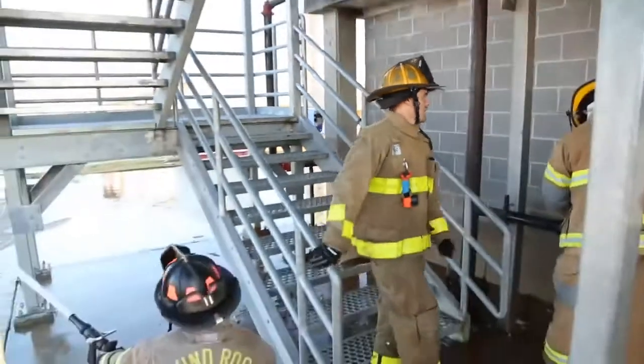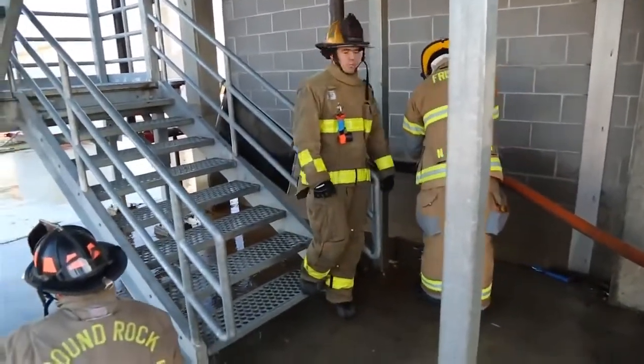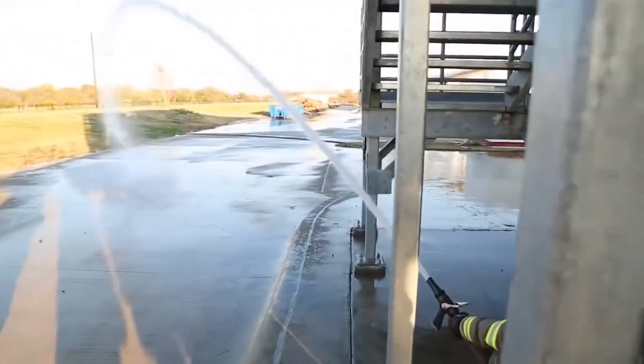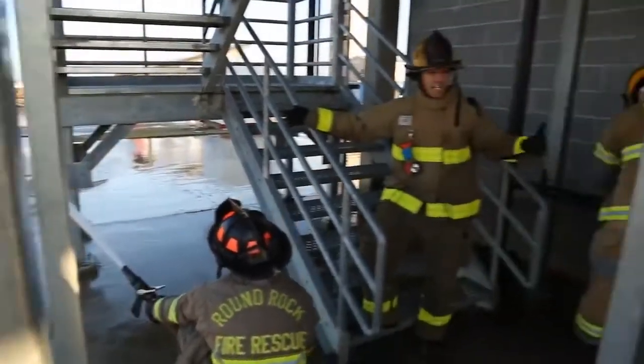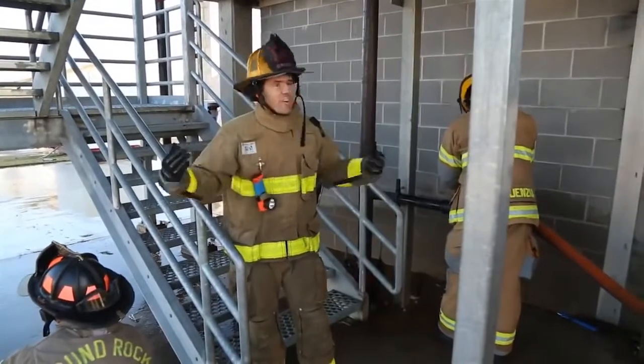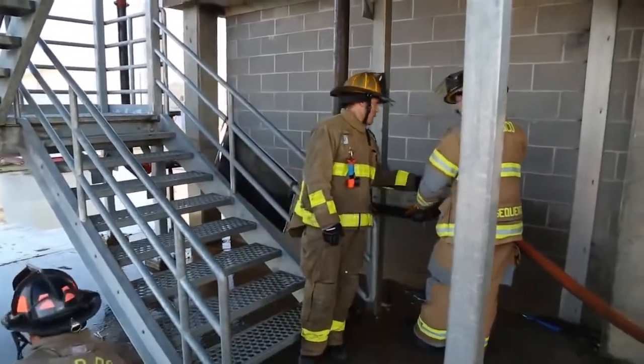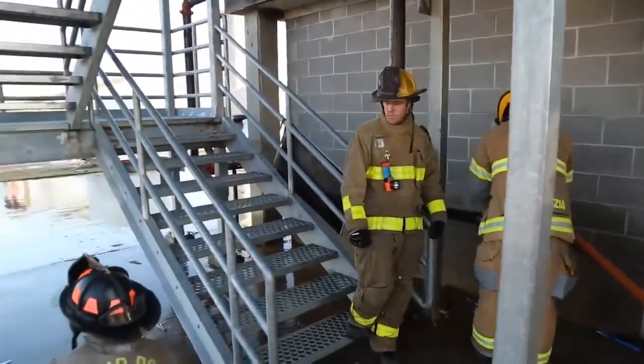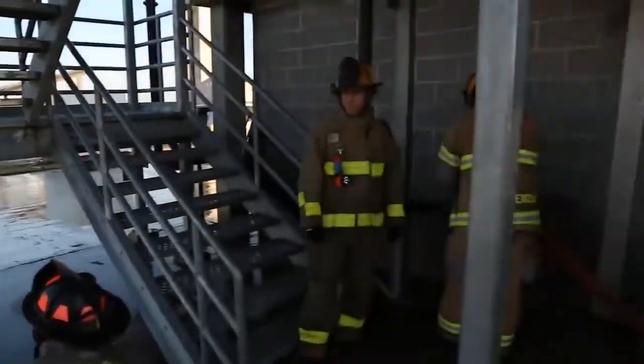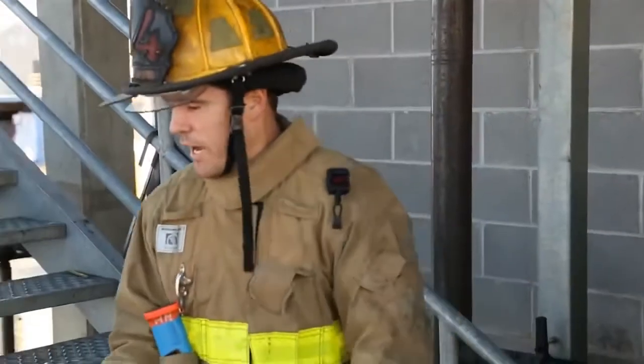What do you see on there? What are we reading? Zero. So almost nothing, right? So keep opening. We have water at the nozzle? Yep. Is that a good stream? I don't like it. That's why we're going to keep flowing. So we're in a stairwell right now, and water is everywhere. It's a mess, but it has to be that way. We got 40. We want to go to 70. 70? All right. We're at 70 psi on our wheel, right?